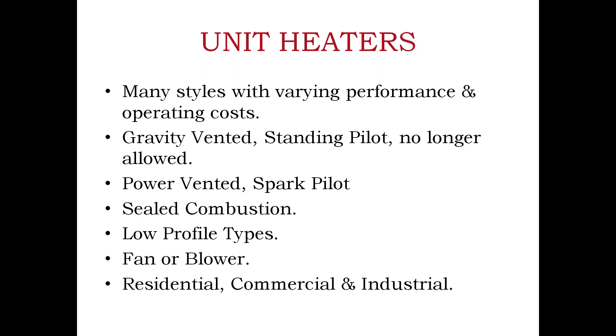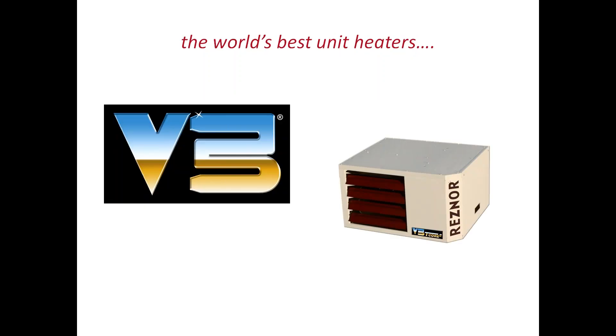The units are available as fan or blower styles. With the blowers, you can add about a quarter inch of static pressure. Our units below 100,000 BTUs are residentially approved. It is the highest efficiency unit in the marketplace — 83% efficient — and carries the best warranty.